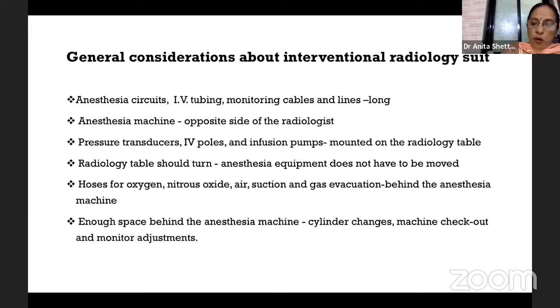Pressure transducers, IV poles, and infusion pumps should be mounted on the radiology table. Hoses for oxygen, nitrous oxide, air suction, and gas evacuation should be behind the anesthesia machine. And there should be enough space behind the anesthesia machine for cylinder checks, machine checkout, and monitor adjustments.